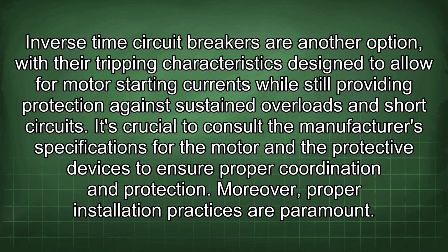Inverse time circuit breakers are another option, with their tripping characteristics designed to allow for motor starting currents while still providing protection against sustained overloads and short circuits. It's crucial to consult the manufacturer's specifications for the motor and the protective devices to ensure proper coordination and protection. Moreover, proper installation practices are paramount.